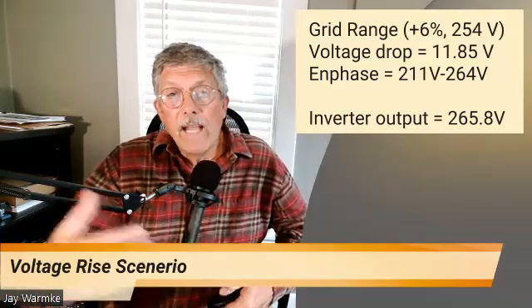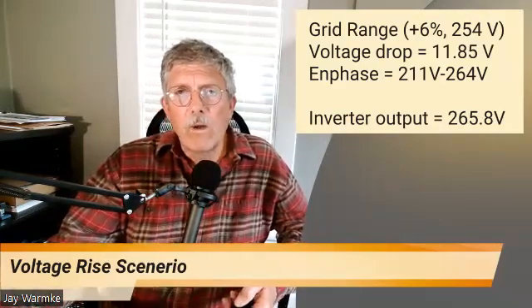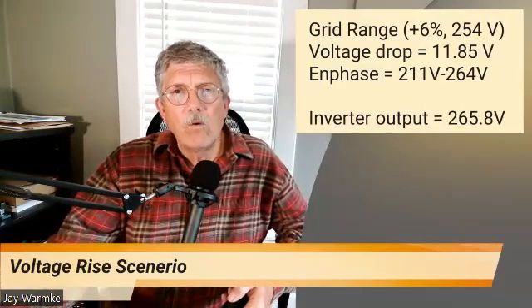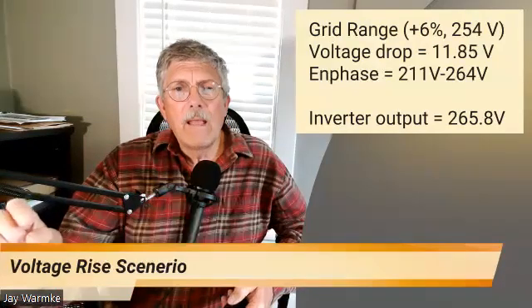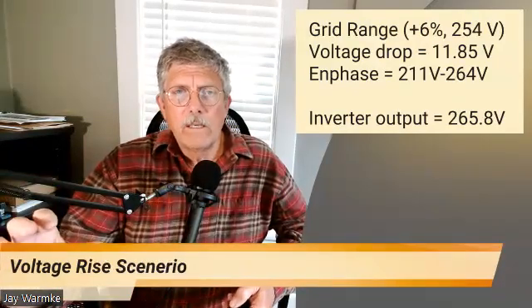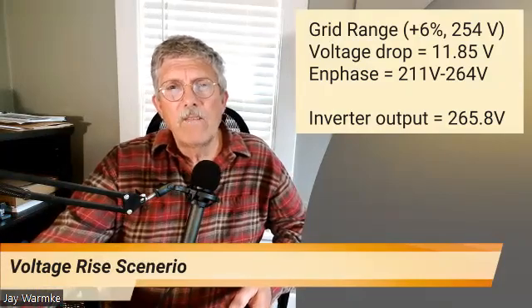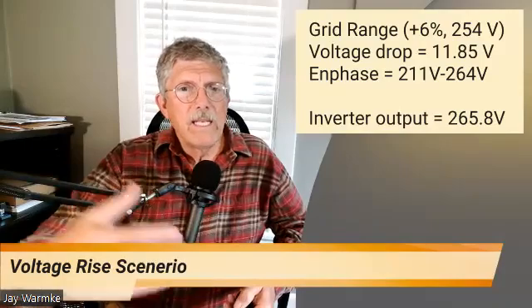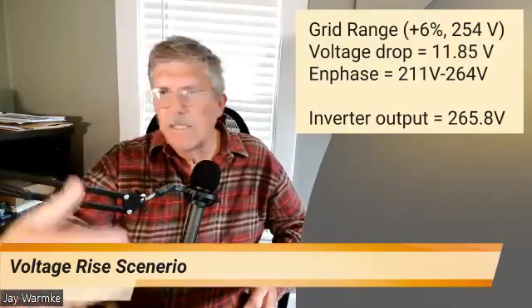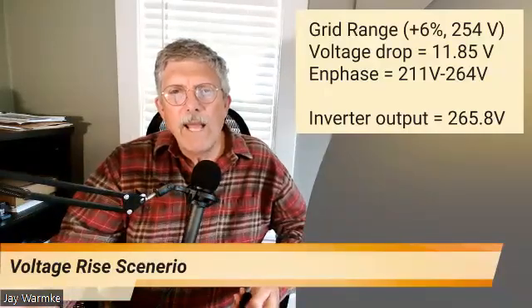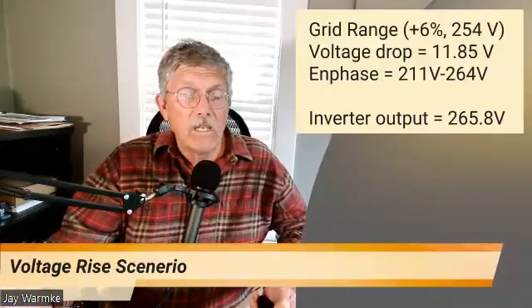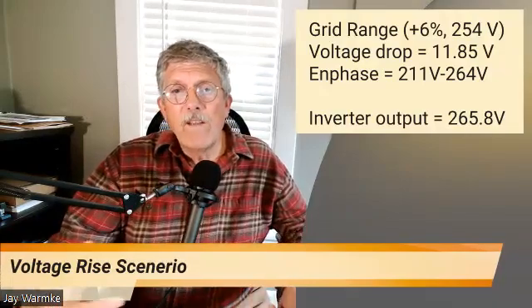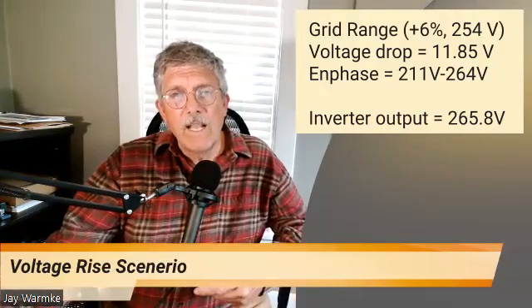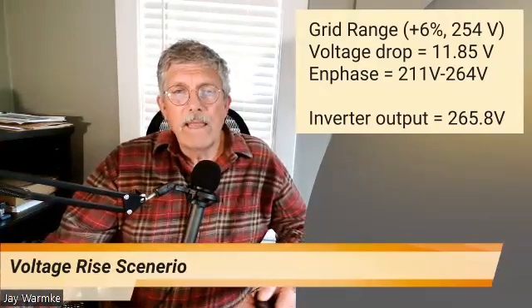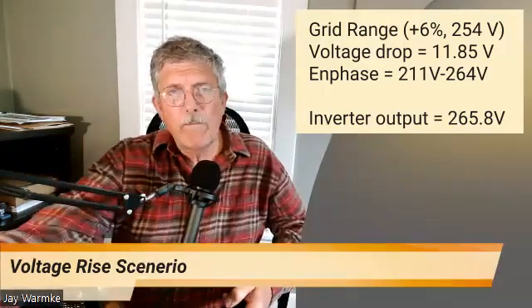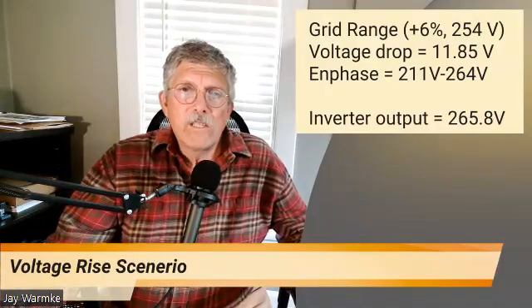And if you had that 12 gauge cable in that 150 foot run and it had an 11.85 volt voltage drop, then the inverter output would have to compensate for that 11.85 volt drop. Plus it needs to match whatever the grid is operating at. So it's going to be at 254. So my inverter output has to be 265.8 volts to match the grid. And the Enphase tolerance levels are between 211 and 264. So at that stage, when that grid voltage spikes up, my inverter is going to shut down.